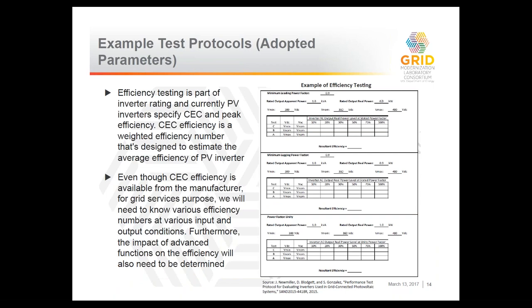Some of the examples: once we have those parameters defined, we can come up with our example test protocol. For example, this one is showing a test protocol for efficiency testing that has currently been done by UL and other NRTLs, nationally recognized test laboratories, when they certify the inverter. This was taken from a recently published report by Sandia, and it is a little bit different from typical CEC testing, because in typical CEC testing you use only unity power factor, but this one looks into 0.9 power factor, lead or lag, because all those new inverters will come with those advanced functions.